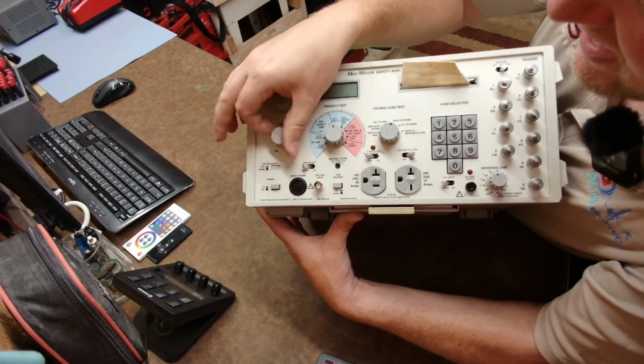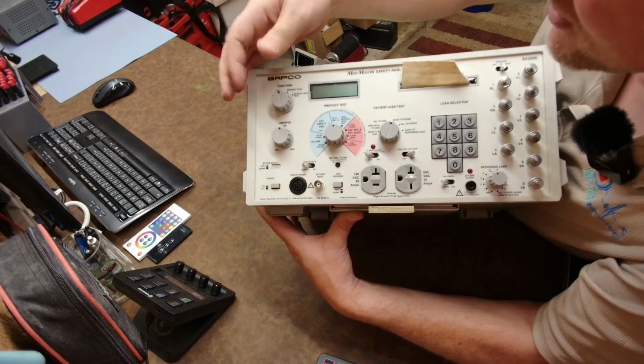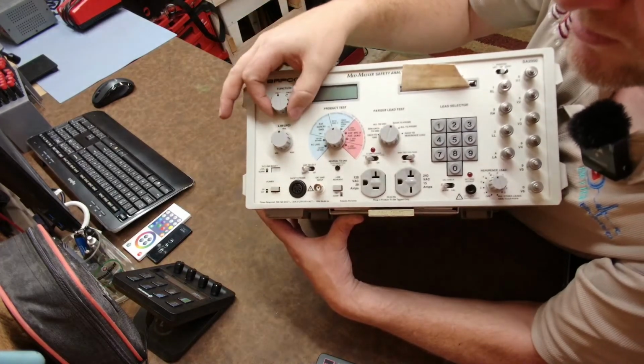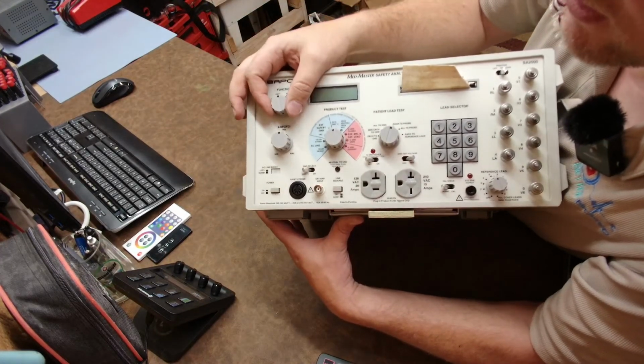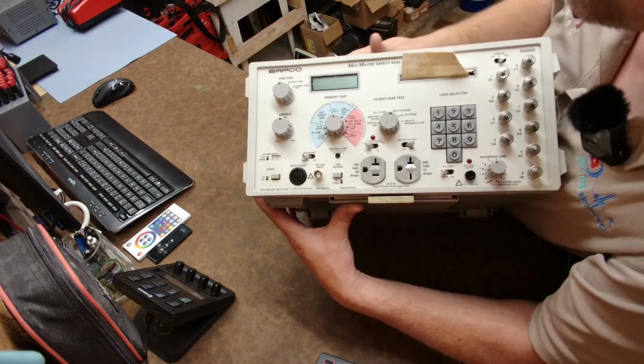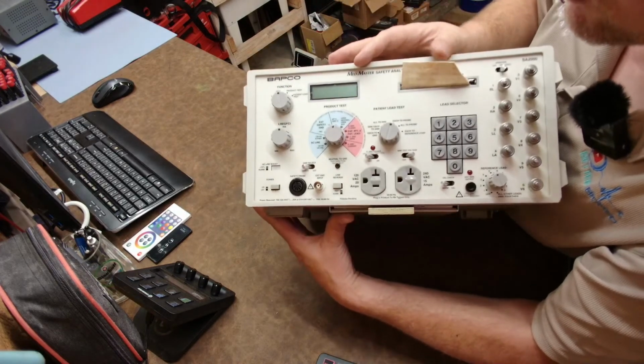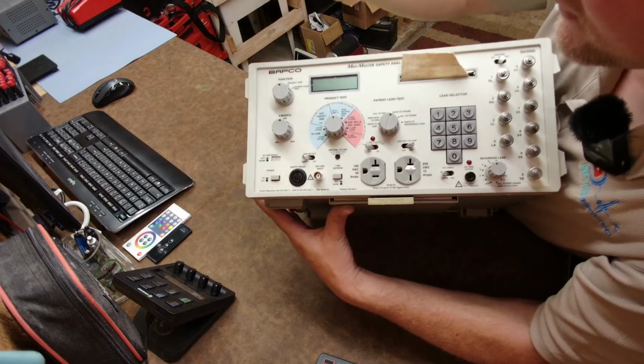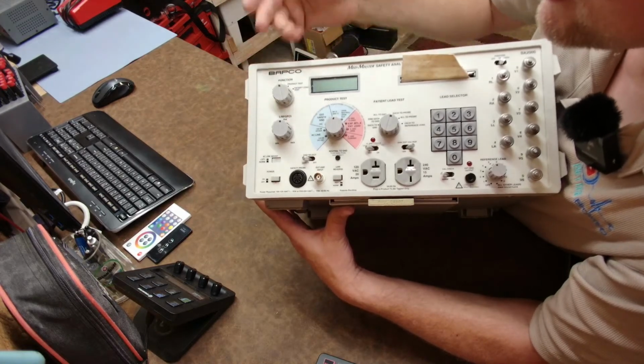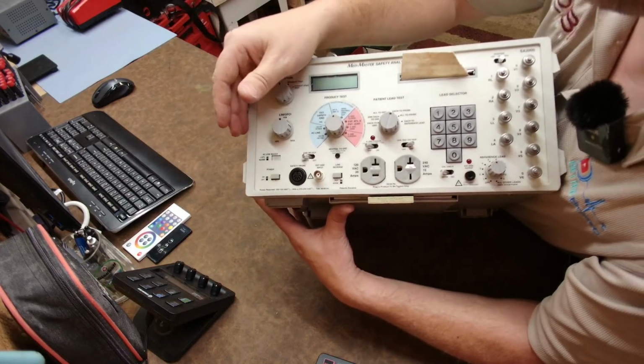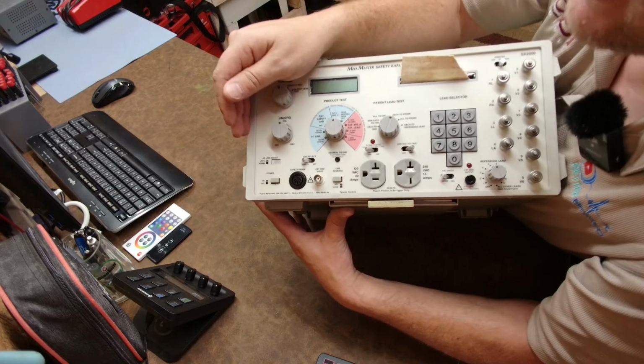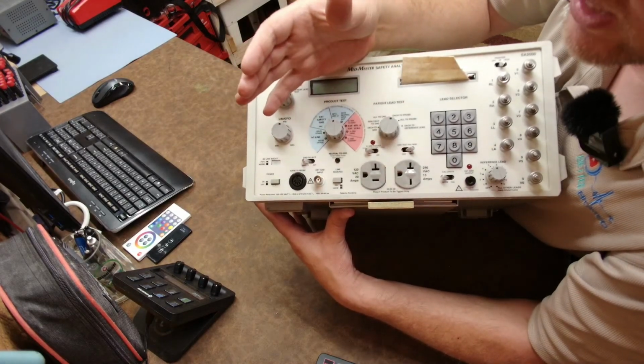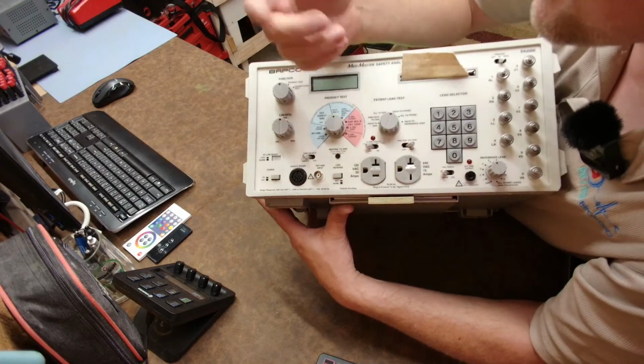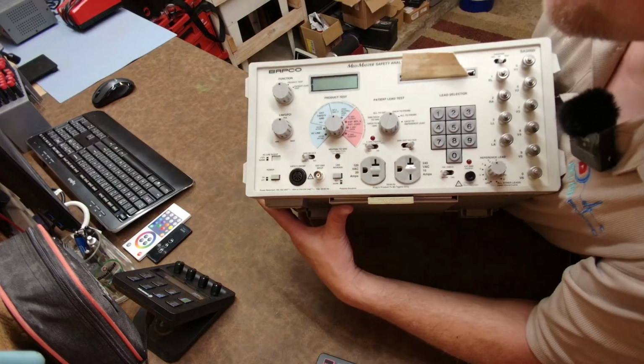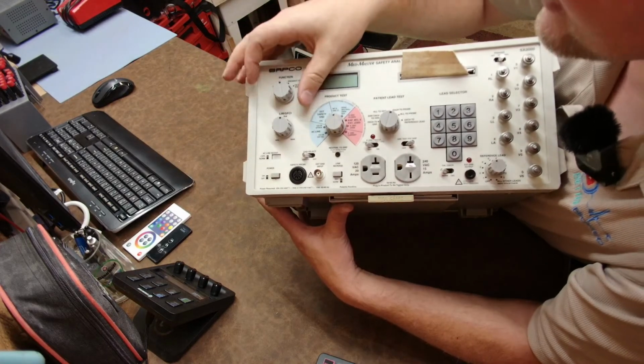It's got a min-max knob, in milliamps. For your LIM, you're allowed to go up to 5 milliamps before it alerts. At 4.5 it should turn amber and give you a warning. It has GFCI and LIM. LIM is basically a hospital version of a GFCI, which is those outlets in your kitchen or bathroom that pop and you have to push the button to reset them.